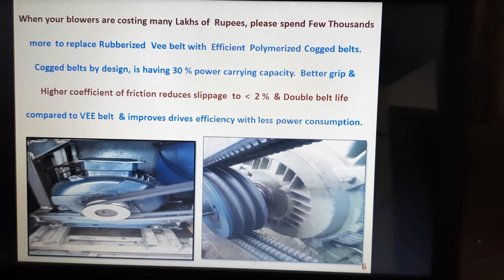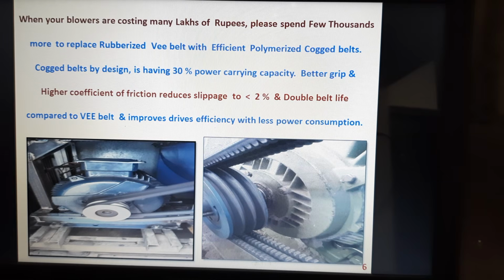When many of your blowers are costing more than lakhs of rupees, please spend a few thousands more to replace the rubberized V-belts with energy efficient polymerized cogged belts. These cogged belts by design have 30% more power carrying capacity, a better grip and a high coefficient of friction, and they keep slippage steady at less than 2%. Their useful life is double that of a V-belt, and they improve drive efficiency with less power consumption.